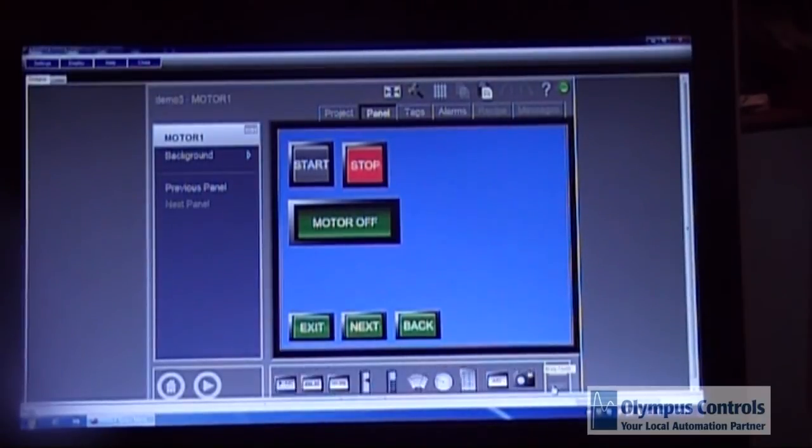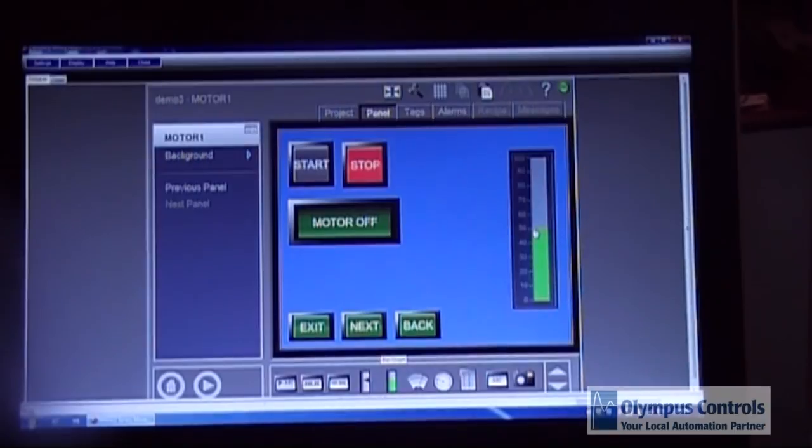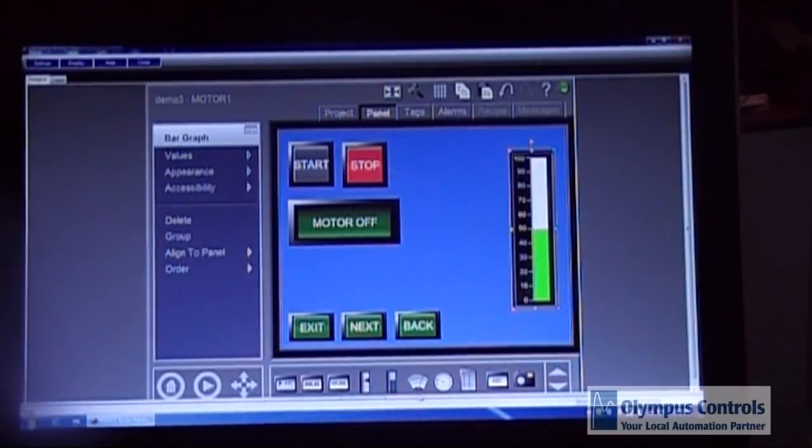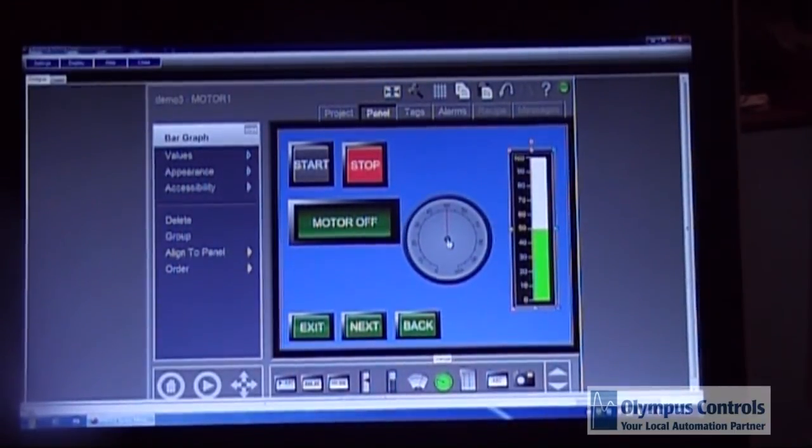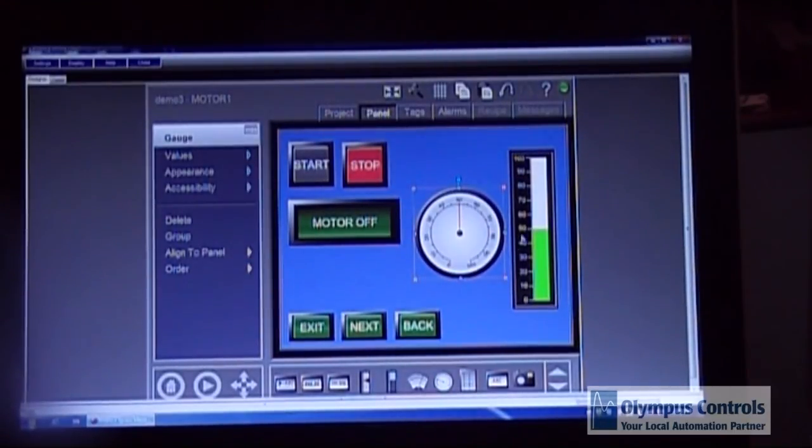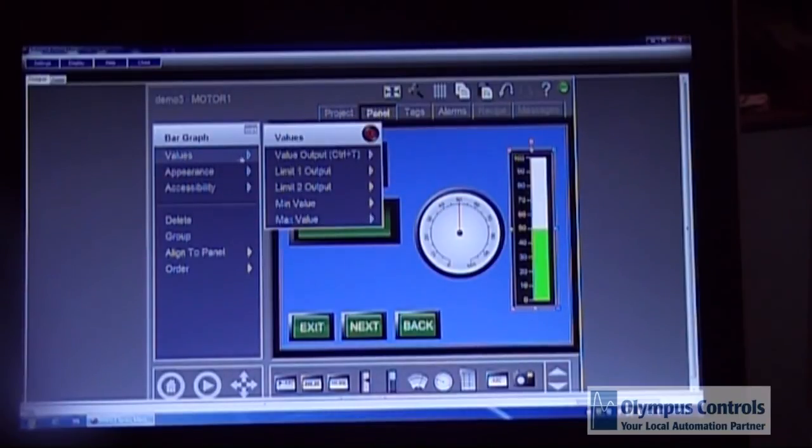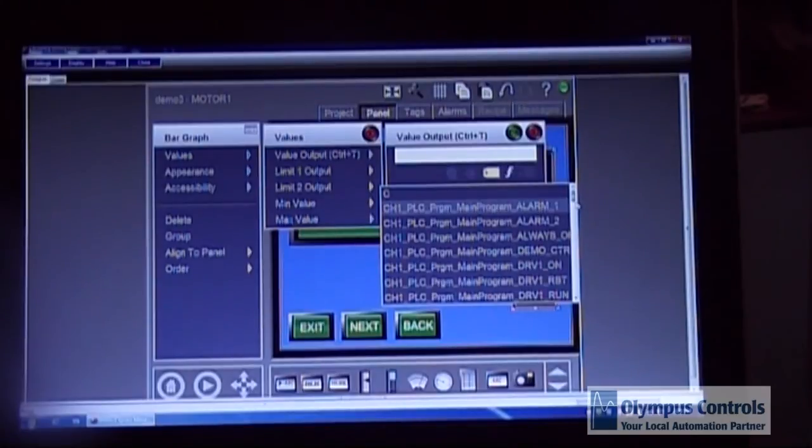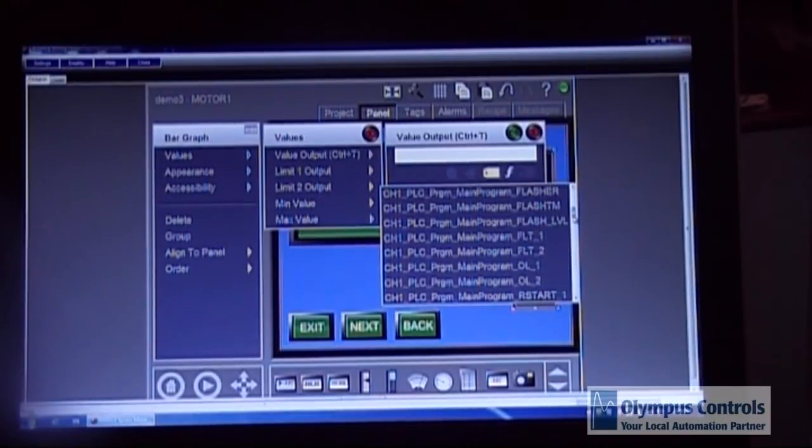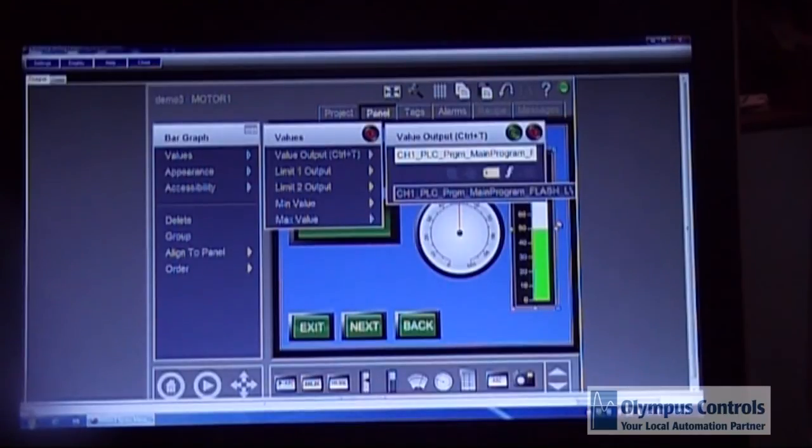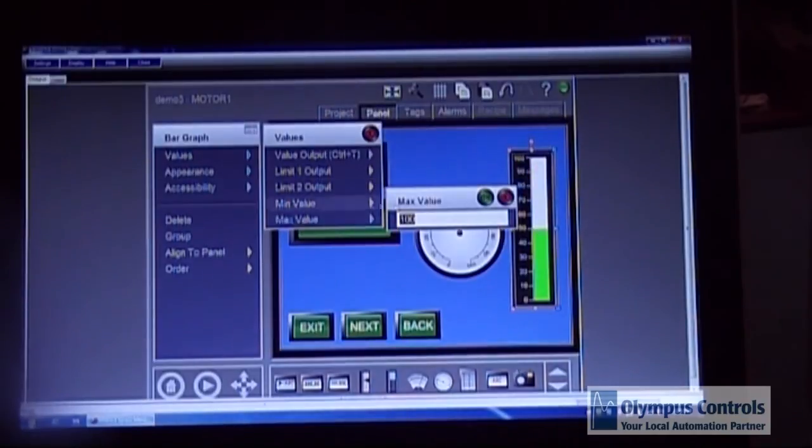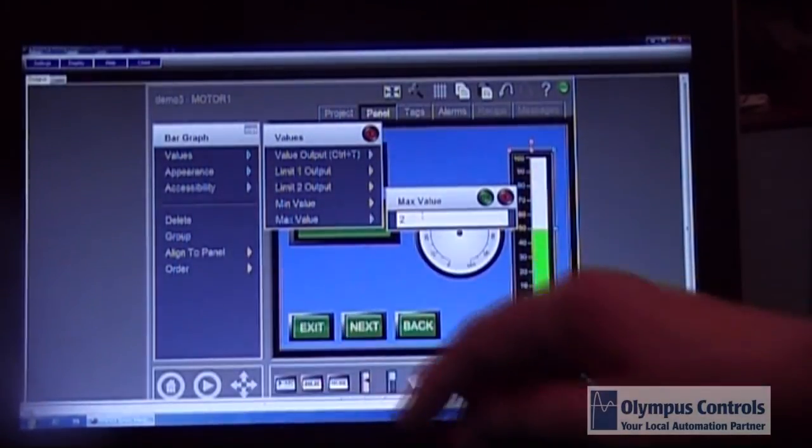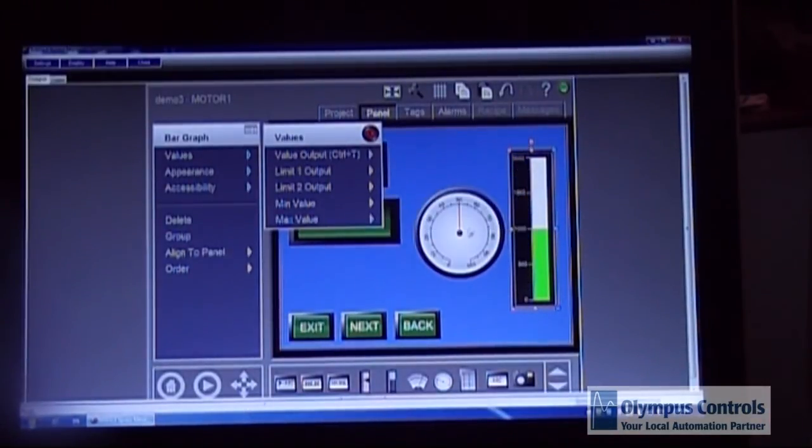Now I'm going to add a bar graph and a speedometer to the screen. It is very similar. You have to choose your tag that's associated with it. In this case I'm using a tag indicating a level from the PLC. You have to tell it what the min and max value are. In this case it is 2000. Click OK.